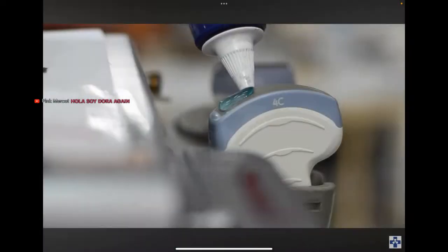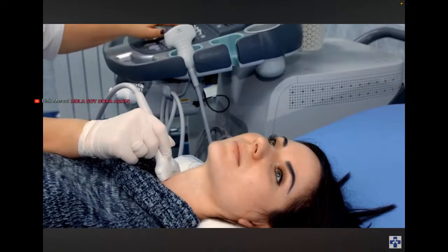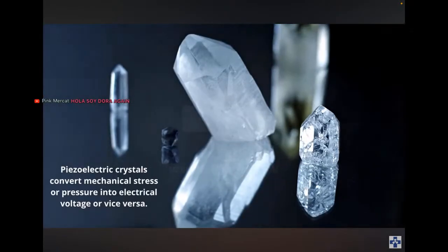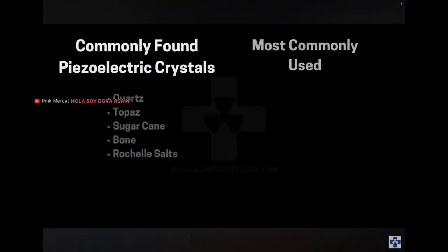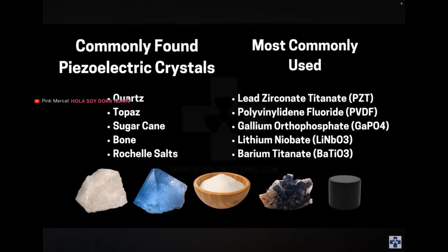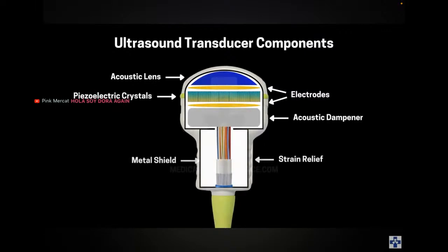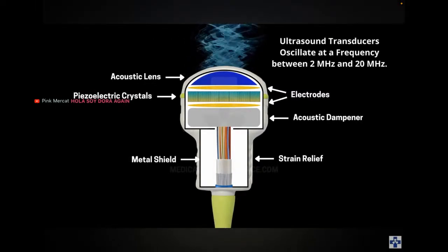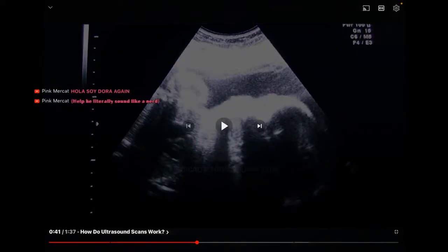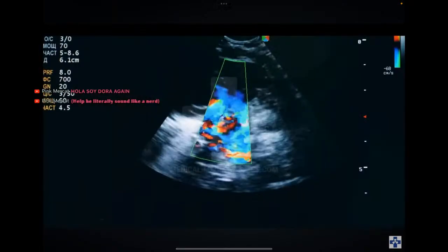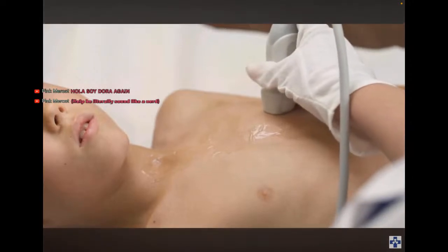The process begins with an ultrasound machine emitting sound waves through a transducer placed on the skin over the area of interest. Ultrasound machines use piezoelectric crystals within the transducer to generate high-frequency sound waves through rapid vibrations. When an electric current is applied to these crystals, they vibrate at a specific frequency, producing ultrasound waves that travel into the body. These ultrasound waves propagate through the skin and underlying tissues. As they encounter boundaries between different tissues or organs, some of the waves are reflected back towards the transducer. The same piezoelectric crystals in the transducer that generate ultrasound waves also act as receivers.